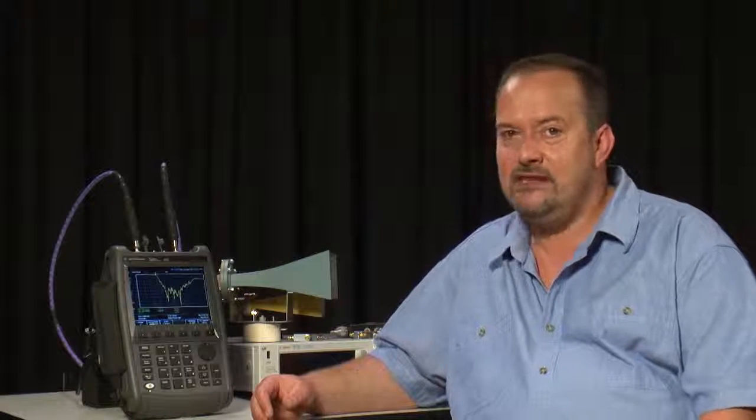At any time, we can save the screen image to the internal memory, an SD card, or to a USB memory stick. We can save the trace data to a TRC or CSV file for later recall and comparison. We can save all our instrument settings to an STA state file, also for later recall, making it easy for less experienced folk to make accurate and high-quality VNA measurements every time.